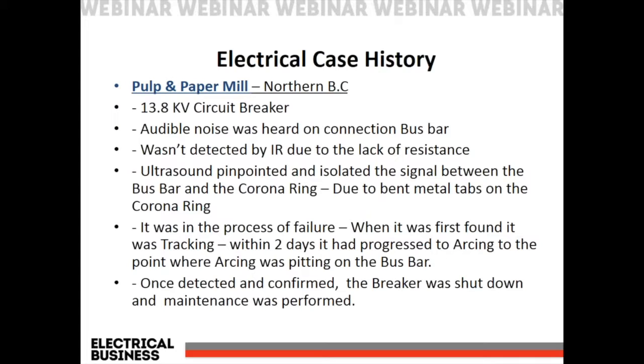And then they took out our ultrasonic detector and recorded the sound and came back and diagnosed it as severe tracking. What was happening was ultrasound pinpointed and isolated the signal between the bus bar and the corona ring, and this was happening due to bent metal tabs on the corona ring. It was causing this tracking. It was basically in the process of failure when it was first found. It was tracking, but within a couple of days later, they went back and did another scan. It actually progressed into arcing at that point, where it was pitting on the bus bar.